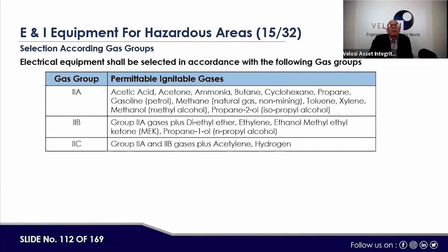Similarly, for permissible ignitable gases, the electrical equipment shall be selected in accordance with the gas group. The second thing is the gas group, from 2A, 2B, 2C. In 2A: acetic acid, acetone, ammonia, butane, propane, gasoline, methane, toluene, xylene, methanol, and so on. Then group 2B is the 2A gases plus diethyl ether, ethylene, ethanol, methyl ethyl ketone. Then group 2C is the group 2A and 2B gases plus acetylene and hydrogen.